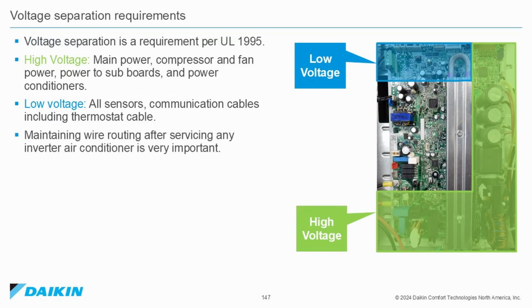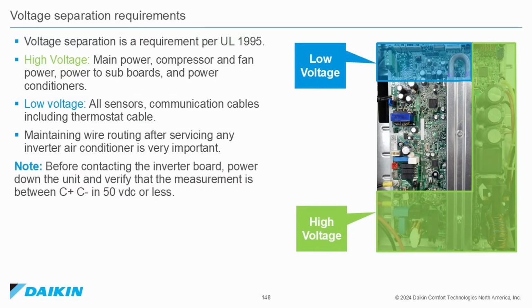Maintaining wire routing after servicing any inverter air conditioner is very important. Before touching the inverter board, power down the unit and verify that the measurement between C positive and C negative is 50 volts DC or less.